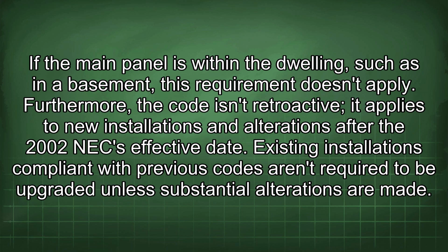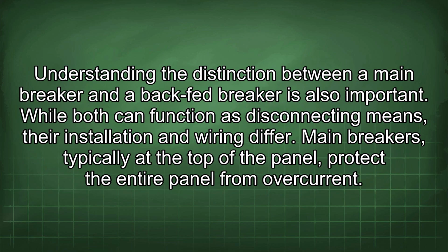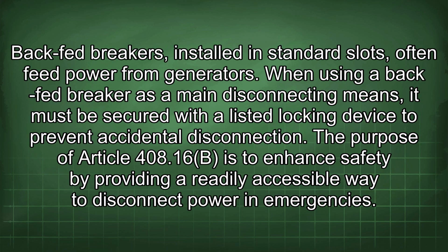Furthermore, the code isn't retroactive. It applies to new installations and alterations after the 2002 NEC effective date. Existing installations compliant with previous codes aren't required to be upgraded unless substantial alterations are made. Understanding the distinction between a main breaker and a backfed breaker is also important. While both can function as disconnecting means, their installation and wiring differ. Main breakers, typically at the top of the panel, protect the entire panel from overcurrent. Backfed breakers, installed in standard slots, often feed power from generators.